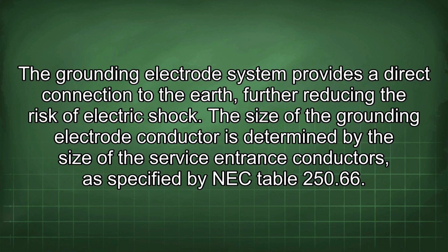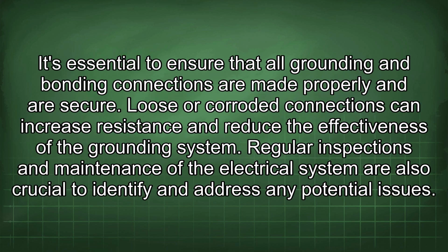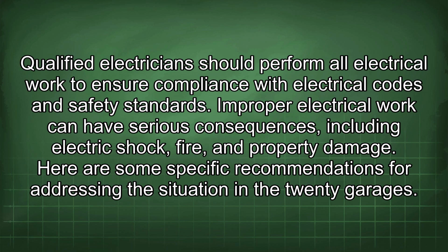The size of the grounding electrode conductor is determined by the size of the service entrance conductors, as specified by NEC Table 250.66. It's essential to ensure that all grounding and bonding connections are made properly and are secure. Loose or corroded connections can increase resistance and reduce the effectiveness of the grounding system. Regular inspections and maintenance of the electrical system are also crucial to identify and address any potential issues. Qualified electricians should perform all electrical work to ensure compliance with electrical codes and safety standards. Improper electrical work can have serious consequences, including electric shock, fire, and property damage.